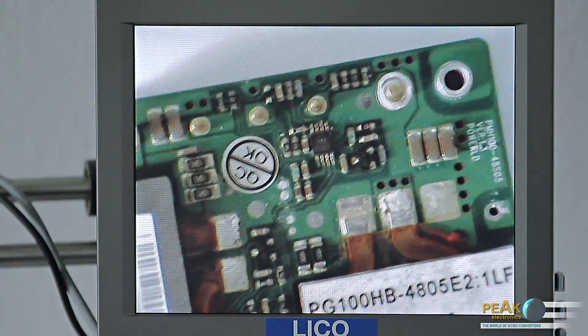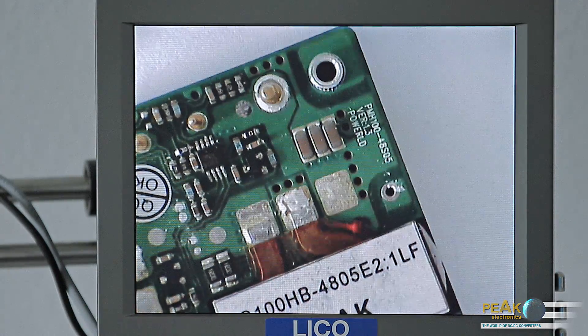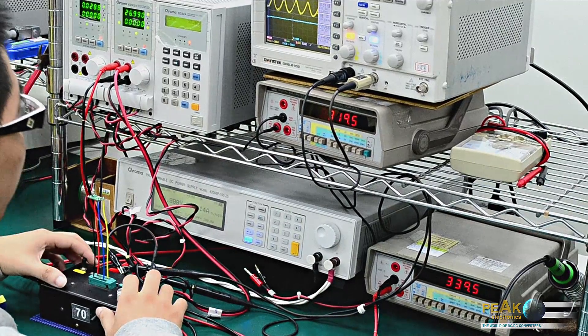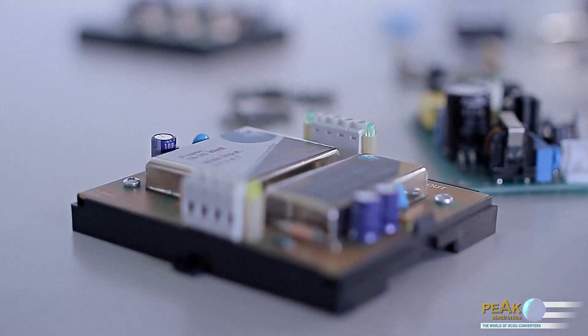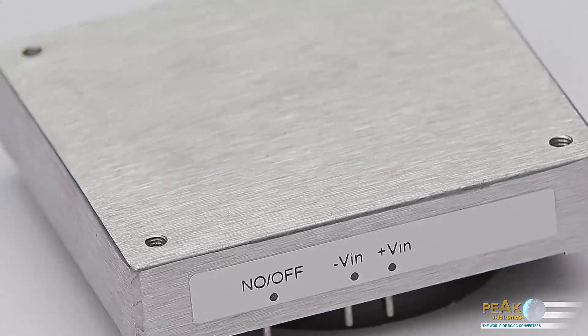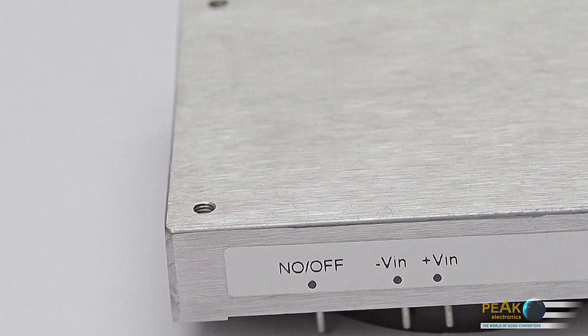Although all converters already have built-in components that reduce the noise generated, in many requirements the standards to be met are more stringent. In such cases, the emitted interference should be further reduced by means of external circuitry. The interferences arise in three areas: between input and output, on the input lines between plus connection and minus connection, and on the output side also between plus connection and minus connection.